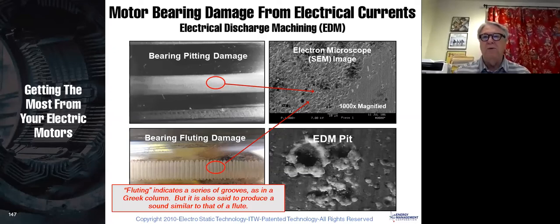If you're looking at it with your naked eye, you can't see that. What you will see is bearing pitting damage. So you will see something, but it looks more like a matting or a less glossy finish on your bearings. Your bearings should always look shiny and glossy, and if you see this matted finish, then that is bearing pitting damage from a variable frequency drive. And if you magnify that, you can see it's composed of all these pits. That is going to cause premature bearing failure.